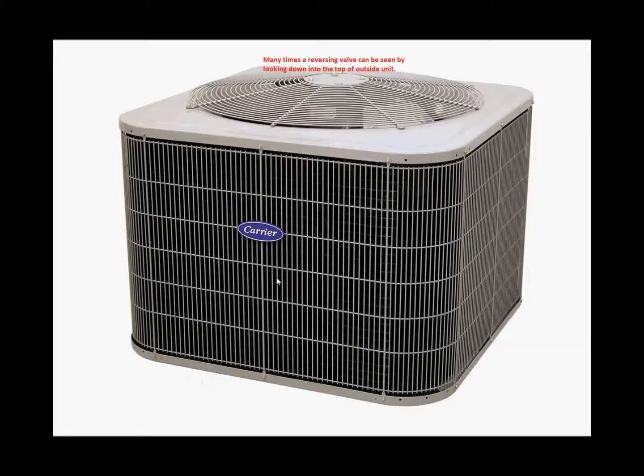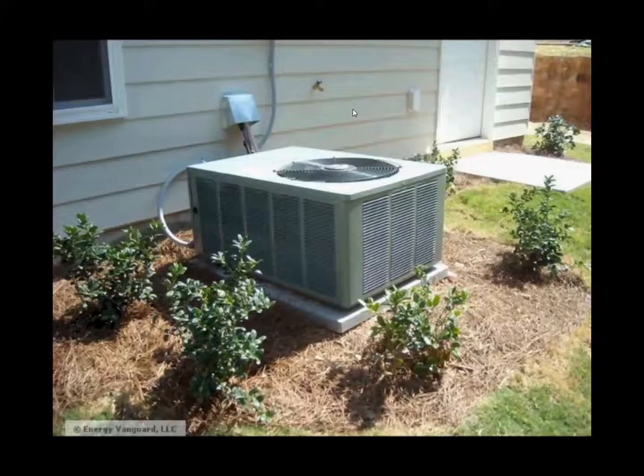Here's a typical outside unit part of a heat pump, and you can see that it has a wire mesh on top, and a lot of times you can look straight down in there and see the reversing valve. Sometimes you can't. In this outside unit, you'll notice that it has a cabinet in this area right here, and sometimes the reversing valve's over in there and you can't always see it. And this might be one of those times when you should text the HVAC technician of your choice the label off of the unit, so he can determine if it is a heat pump.